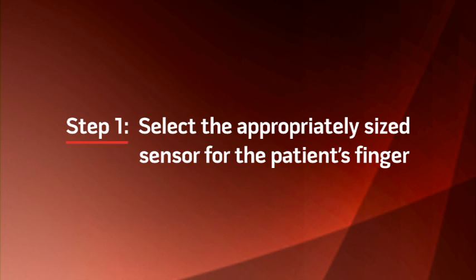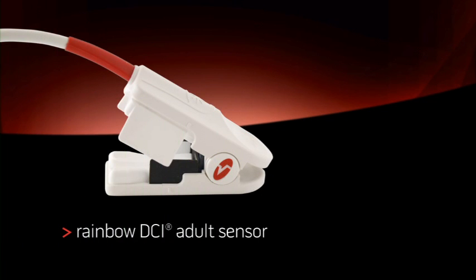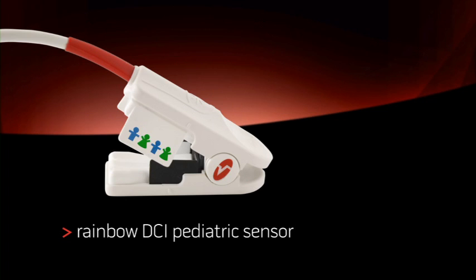There are several simple but very important steps you must follow for proper rainbow sensor placement. Step 1. Select the appropriately sized sensor for the patient's finger. For adults with average to large sized fingers, use the adult sensor. For patients between 10 and 30 kilograms, and for adults with slender fingers, use the pediatric or small finger sensor. The rainbow sensor should be used on fingers only. Using the rainbow sensor on toes or earlobes, even on pediatric patients, will cause inaccurate readings.